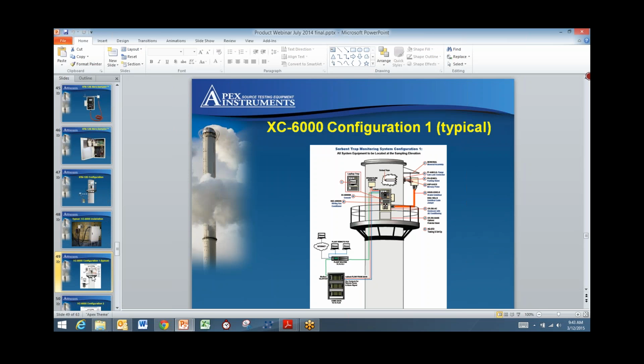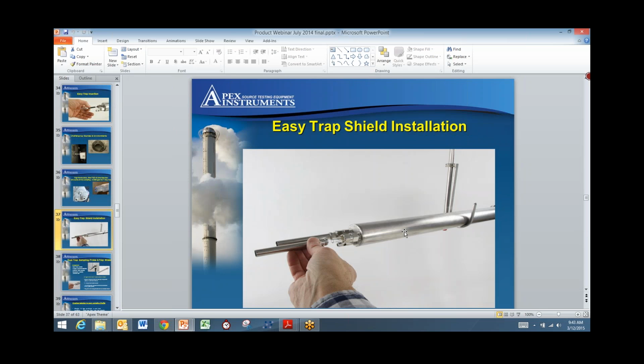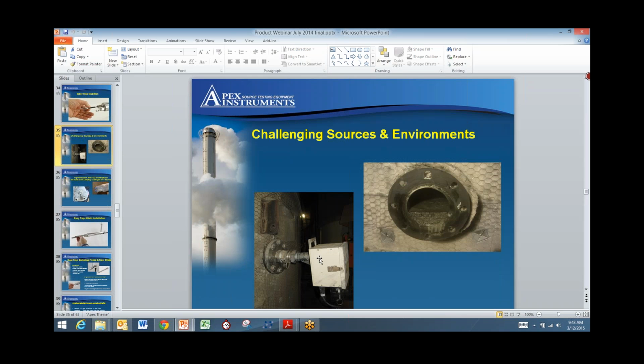Any more questions on the hardware or the unit itself, anything like that we can answer for you? Oh, I'm good. Go down. Yeah, that's that J-hook I was talking about to allow you to hang the probe off the monorail system. And then you can see some shots there of the probes going into the. We have a cam lock and groove fitting here, so we can supply a flange with a packing gland that's attached to the probe. So what you can do is insert this into your stack and lock it down so it won't go anywhere. So basically, when you're doing your trap changes, it doesn't take any tools. You just pop the cam lock and slide the probe out, change them, slide it back in.